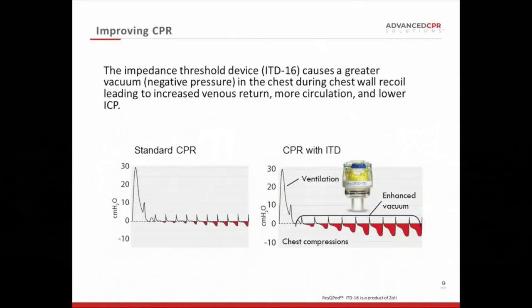We'll start with the impedance threshold device, also known as the ITD16 or the ResQPOD. This device is attached to the airway. Comparing intrathoracic pressure curves with standard CPR alone versus CPR with the impedance threshold device: on the left, without the device, you see a rise in intrathoracic pressure and then a tiny vacuum that develops as the chest recoils. On the right, a greater vacuum develops inside the thorax, which sucks more blood back into the heart and lowers intracranial pressure. This results in improved circulation — in fact, it doubles blood flow to the heart and the brain with just a pair of hands. But you have to do high-quality CPR: about 100 to 110 compressions per minute, 2 inches of chest compression, with full chest wall recoil.